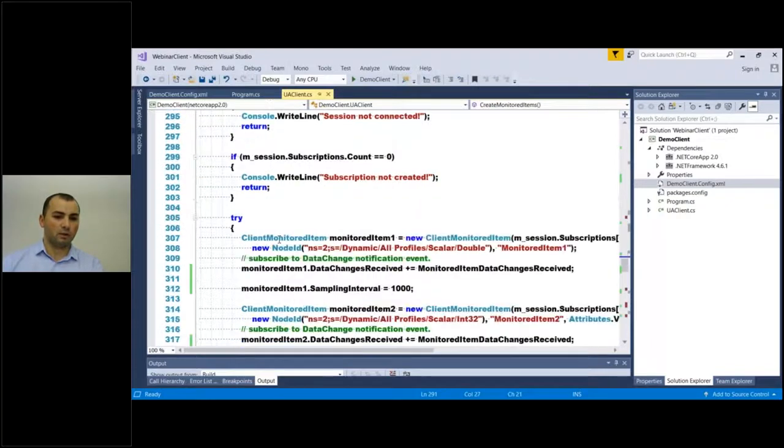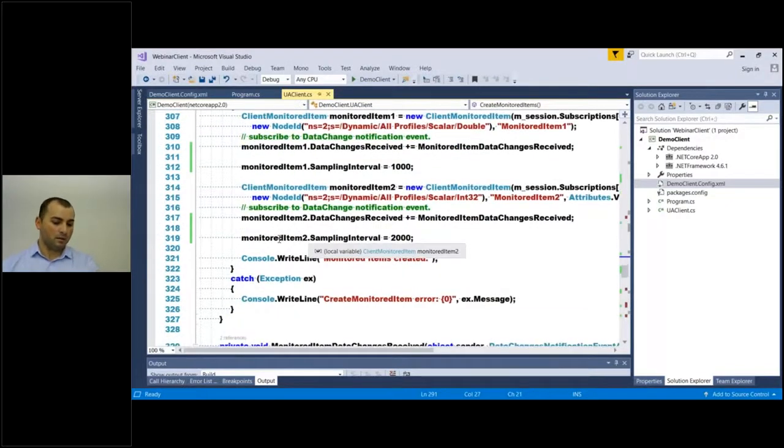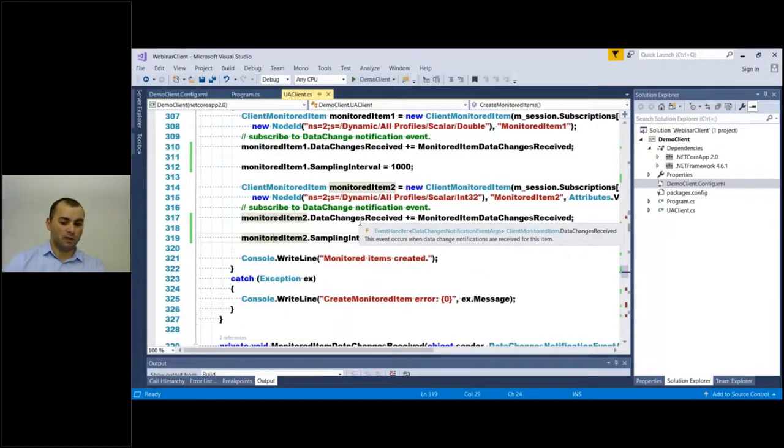You have to create a monitored item for the event notifier attribute, and that, instead of triggering data change notifications, will trigger event notifications. For alarms, you will have to further use the method call functionality. So you'll have to call methods for confirming or other actions on the alarm nodes.